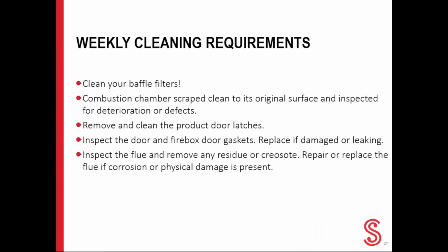Now we're going to discuss some weekly cleaning requirements. These include removing and thoroughly cleaning the kitchen baffle filters. The baffle filters must be cleaned at a minimum of once per week. There are times baffle filters may need to be cleaned as often as daily, such as when kitchens are cooking large amounts of proteins like burgers and steaks.